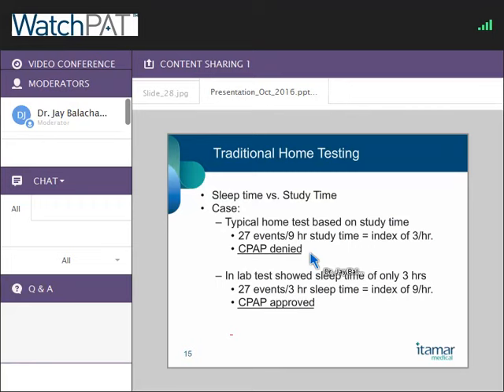Another question: I have seen WatchPAT studies that don't detect REM sleep — is it possible for an individual not to have REM sleep all night? Yes. REM sleep is detected by increased sympathetic tone detected by the PAT probe and increased pulse rate variability. If a patient has medications that suppress pulse rate variability and sympathetic tone change, you may have a reduction in the ability to detect sleep stages — but not respiratory events. Event detection is still great, but sleep stage detection will fall off with such medications. And yes, it is certainly true that patients for a number of reasons may not have REM sleep on a study night, which can be medication-related or otherwise.